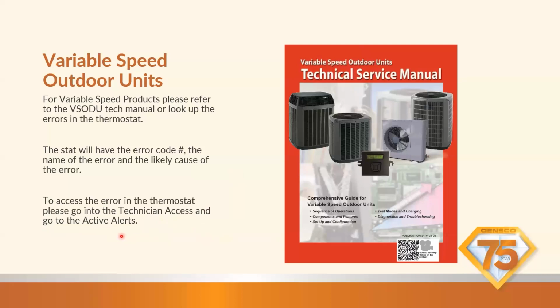And they're pretty accurate. Are they 100% accurate? Not always. Sometimes you have multiple errors and you kind of have to piece them all together to see what makes sense when you have 2 or 3 errors. What could it be? You look at those 3 errors, put them together. But when it comes to the variable speed, there's not going to be a very simple flash code at all. So you're going to need to go to the thermostat and look it up. And there could be like 100 different errors. So I'm not going to try and go through every single one of those errors and waste too much of everyone's time. That's really it for this one, guys.